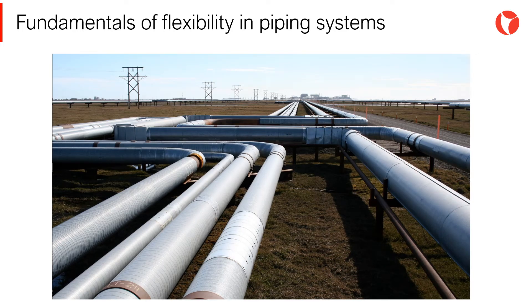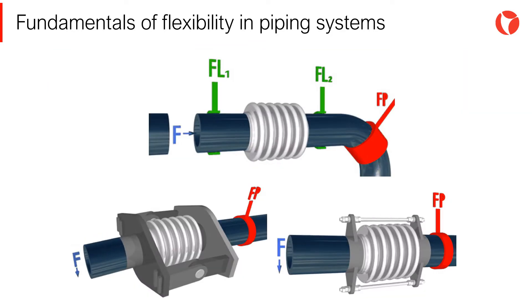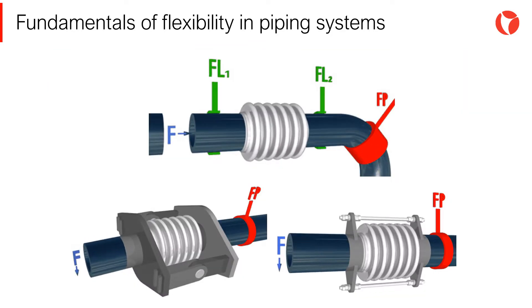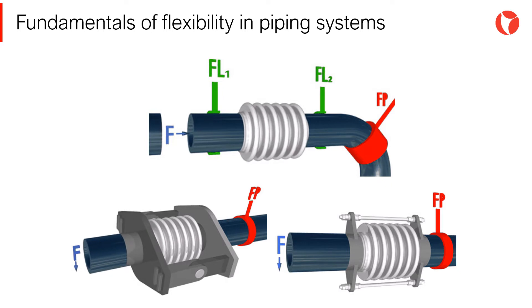With the exception of straight piping sections, all piping systems have varying degrees of flexibility depending on their configuration. When the changes in direction of a piping system required by the location of the equipment do not provide sufficient flexibility, expansion loops are often used. An expansion joint is a mechanical device designed to absorb expansion and contraction induced by temperature changes in the piping system.